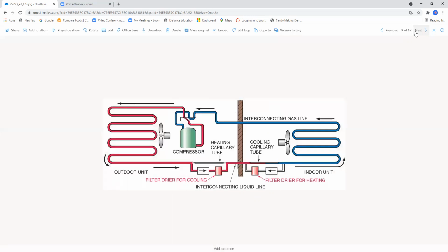Okay, here we have basically a heat pump system. This was covered in the previous PowerPoint lecture. Notice that we're utilizing a capillary tube as our metering device. Notice that we have a filter dryer and a check valve for each metering device. So basically our metering device consists of a capillary tube and the check valves. And then notice that we have filter dryers for each segment. Typically, you're only going to find one filter dryer for the whole thing in the new systems. This was just one type of system that was manufactured years ago.